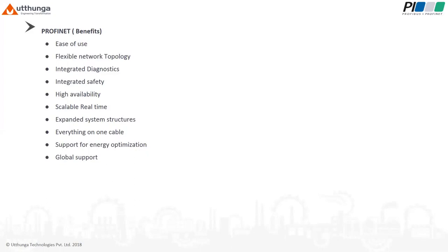Integrated diagnostics. PROFINET includes intelligent diagnostic concepts for field devices and networks. Cyclic diagnostics data transmission provides important information regarding the status of the device and network, including a display of the network topology. Integrated safety. The plant owners and plant people know this. ProfiSafe is widely developing nowadays. ProfiSafe is the integrated safety solution of PROFINET that reduces the wiring immensely in the network.